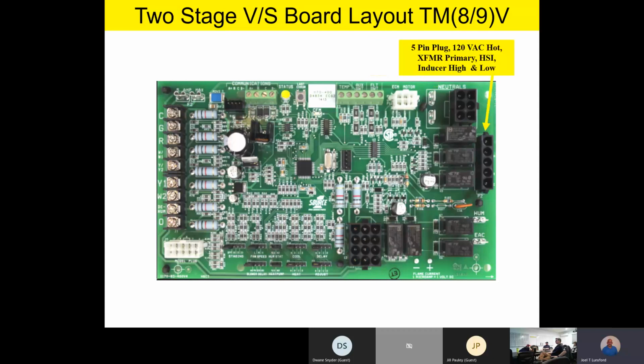Coming down the side of the board, you're going to notice there's a 5-pin plug. Now that 5-pin harness is going to feed 120 volt to, for instance, our transformer primary and our hot surface igniter, as well as our high and low inducer speeds. So this is all going to be harnessed in from the factory, but I've taken all the harnesses off so we can talk about all the features on the board. But this is where we have this 120 volt output to our transformer primary, our hot surface igniter, and then our high and low on our inducer draft blower as well.